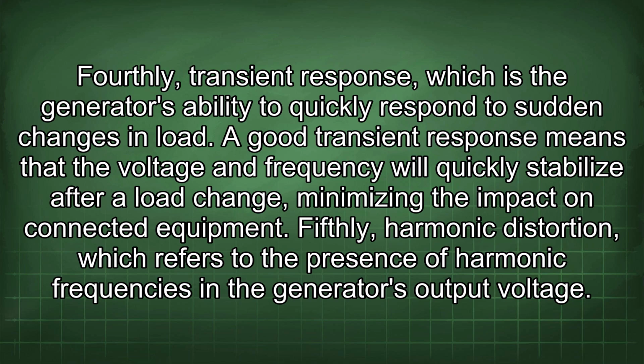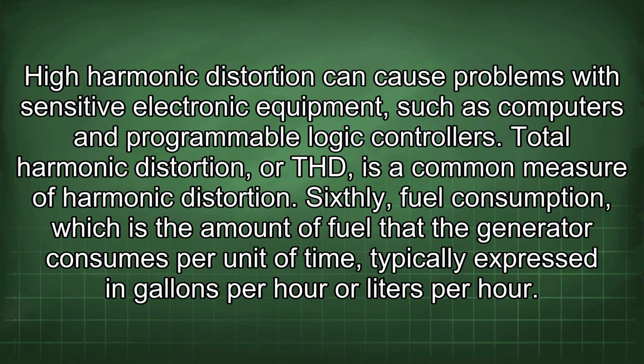Fifthly, harmonic distortion, which refers to the presence of harmonic frequencies in the generator's output voltage. High harmonic distortion can cause problems with sensitive electronic equipment, such as computers and programmable logic controllers. Total harmonic distortion, or THD, is a common measure of harmonic distortion.